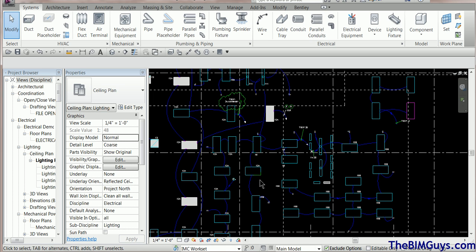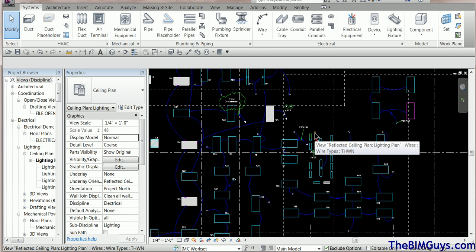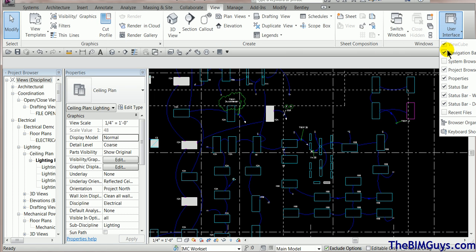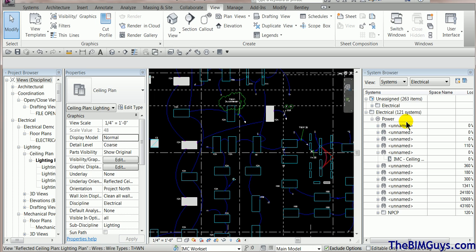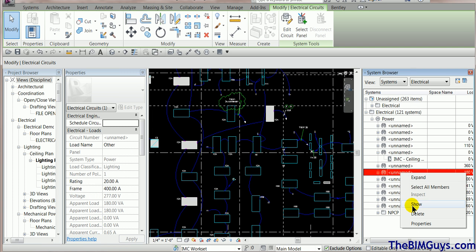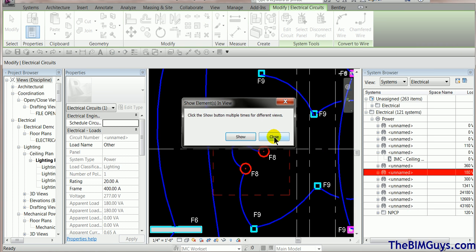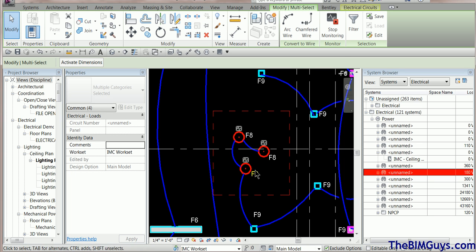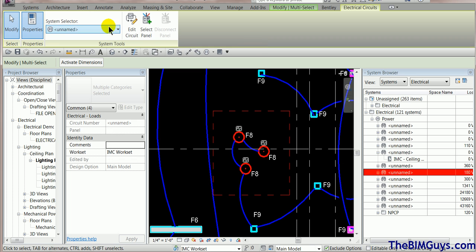Now, how can you find these weird little groups that are not circuited? One tip is to use filters, which we'll cover in another video. But let's look at a tool in Revit called the System Browser, located under View > User Interface > System Browser. When you fire it up, it shows you all the unnamed circuits. If you select one, right-click, and hit Show, it navigates you right to that fixture — and you can see these three fixtures don't have a circuit.